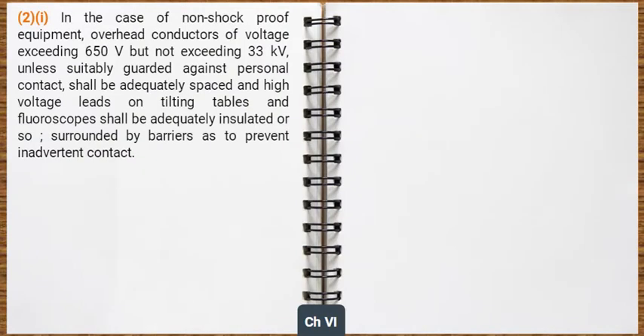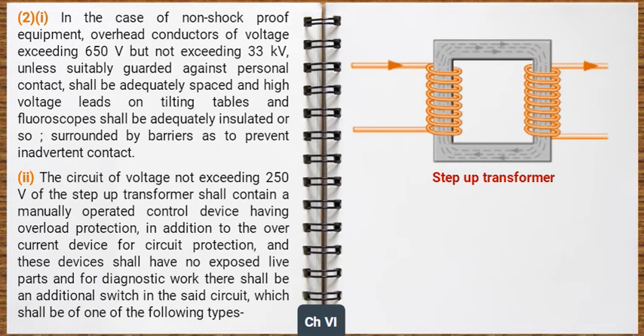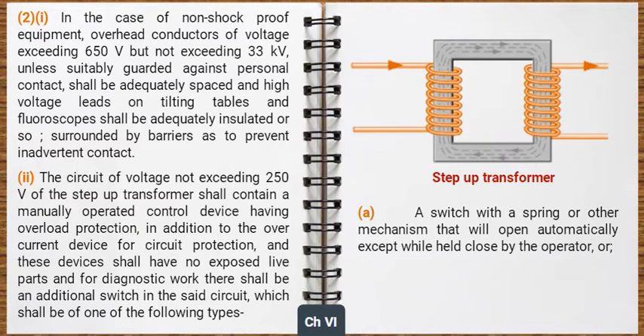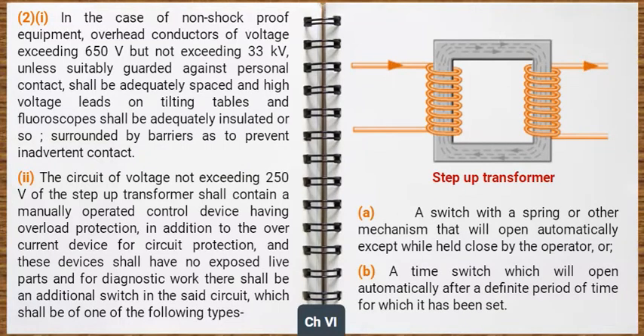In the case of non-shock-proof equipment, overhead conductors of voltage exceeding 650 volt but not exceeding 33 kilovolt, unless suitably guarded against personal contact, shall be adequately spaced, and high voltage leads on tilting tables and fluoroscopes shall be adequately insulated or so surrounded by barriers as to prevent inadvertent contact. The circuit of voltage not exceeding 250 volt of the step-up transformer shall contain a manually operated control device having overload protection in addition to the overcurrent device for circuit protection, and these devices shall have no exposed live parts, and for diagnostic work there shall be an additional switch in the said circuit which shall be of one of the following types: a switch with a spring or other mechanism that will open automatically except while held closed by the operator, or a time switch which will open automatically after a definite period of time for which it has been set.